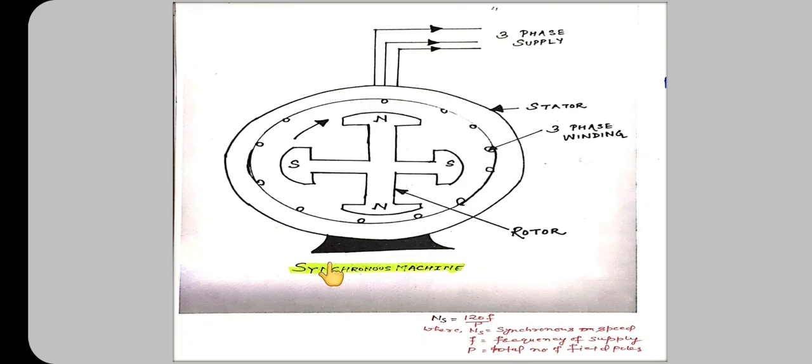In case of a rotating armature, the load circuit is required to be connected with the armature winding by means of slip rings and brushes, in which case a difficulty is experienced in collection of heavy current at very high voltages.